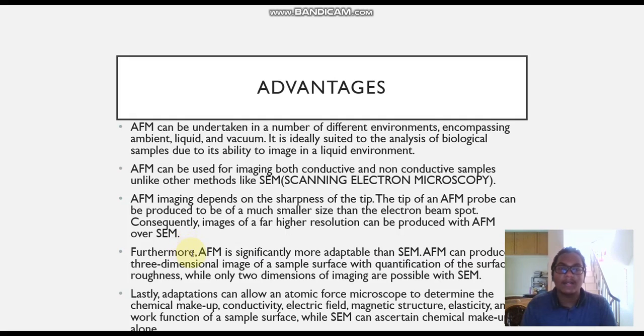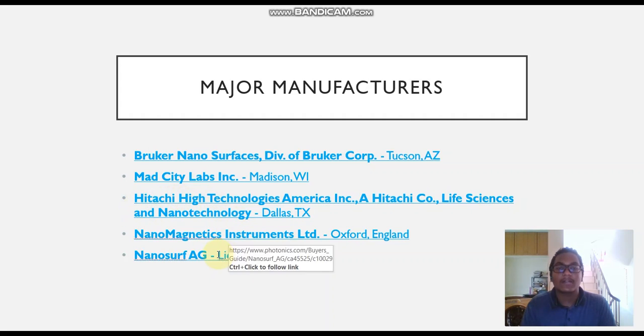Now, when compared to the SEM, AFM can produce a three-dimensional image of the sample surface with quantification of the surface roughness, while only two dimensions can be produced in the SEM. Lastly, adaptations can help to determine the chemical makeup, conductivity, electric field, magnetic structure, elasticity, and work function of the sample surface. Whereas in SEM, only the chemical makeup can be ascertained. Now, when we talk about the major manufacturers, these are all in the US, Arizona, Wisconsin, Dallas, Texas, and these are Bruker Nanosurfaces, Mad City Labs Incorporated, Hitachi High Technologies, one in England known as Nanomagnetics Instruments, and NanoSurf AG in Switzerland.